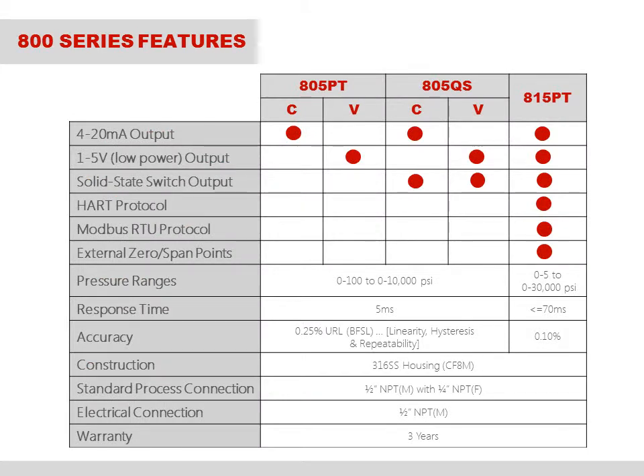Let's do a quick comparative analysis of the Series 800 family of pressure transmitters. As you can see, all three provide a 4 to 20 milliamp and a 1 to 5 volt DC outputs. Both outputs are standard with the 815PT. However, with the 805PT and the 805QS, the output must be specified in the model number. Let's take a look at an example. An 805 PTC provides only a 4 to 20 milliamp output, and a 805 PTV provides only a 1 to 5 volt DC output. The same applies to the 805 QS.